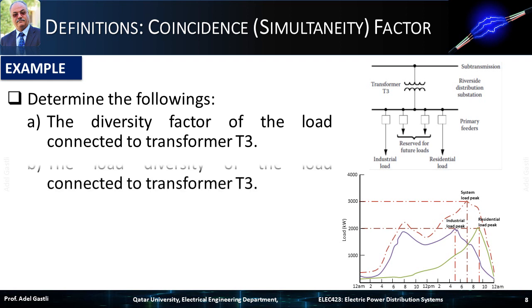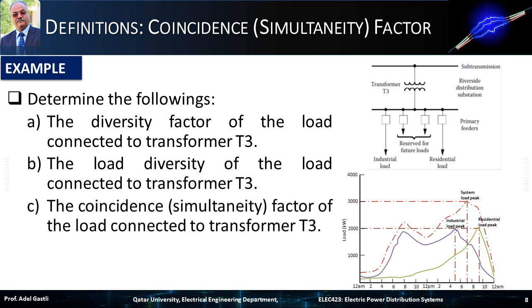Summing the two loads leads to the total transformer load curve shown in the figure, with a maximum of 3,000 kW occurring at 7 p.m. We need to determine the following: the diversity factor of the load connected to the transformer, the load diversity of the load connected to the transformer, and the coincidence or simultaneity factor of the load connected to the transformer.